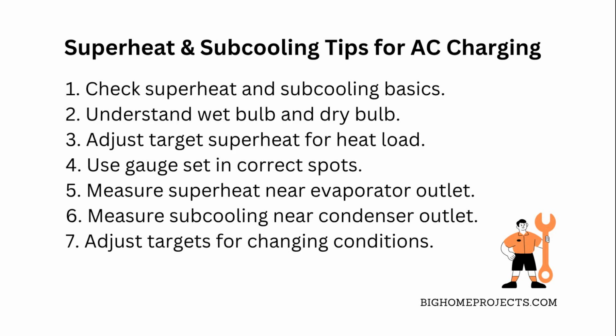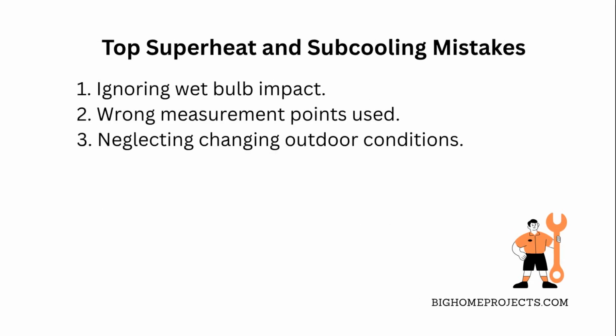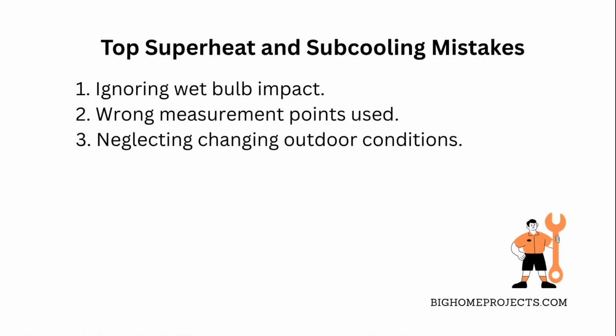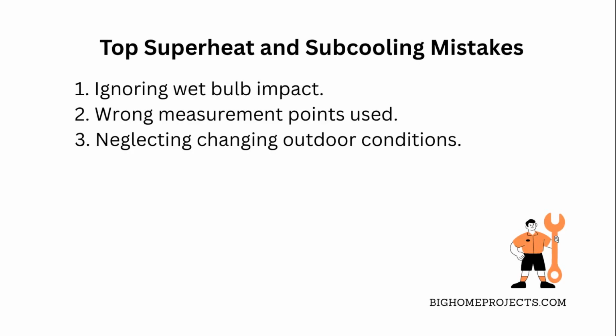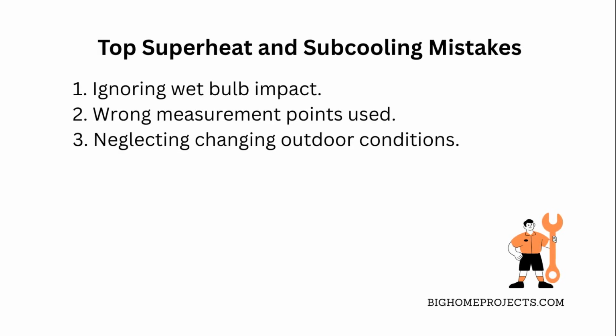One of the biggest mistakes people make when interpreting superheat and subcooling is assuming the gauge reading alone tells the whole story without cross-referencing a PT chart or app. This leads to wrong temperature matches and bad system diagnostics. Another common issue is mixing up refrigerant types. Each refrigerant's pressure-temperature relationship is unique, so guessing or using the wrong chart can throw off your entire assessment.